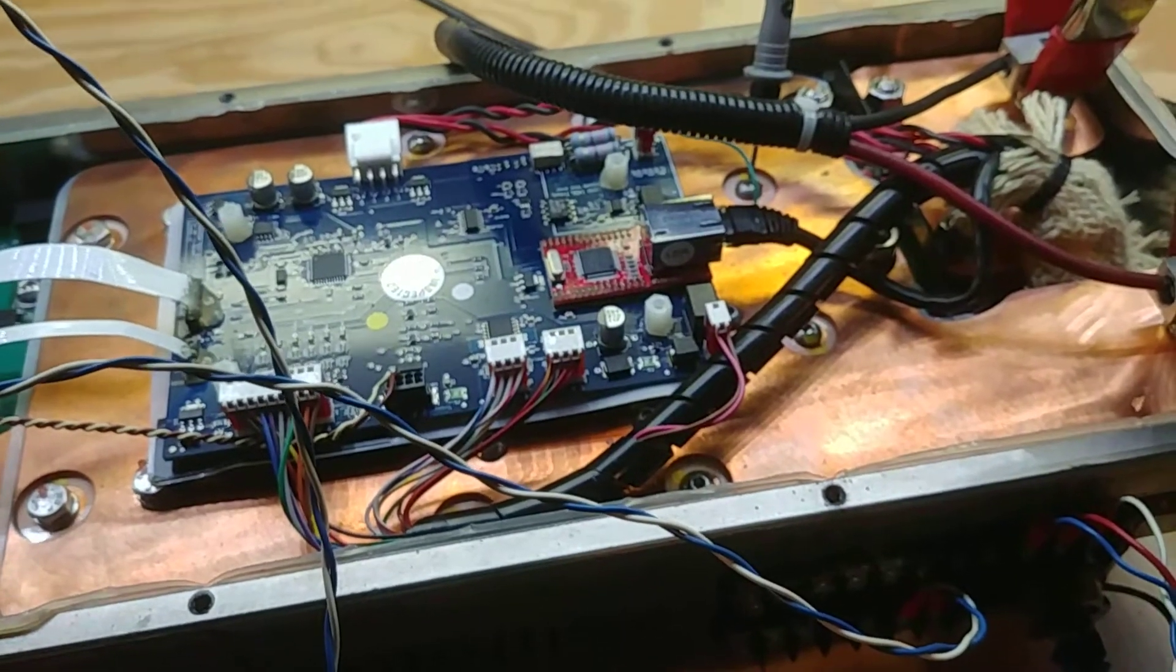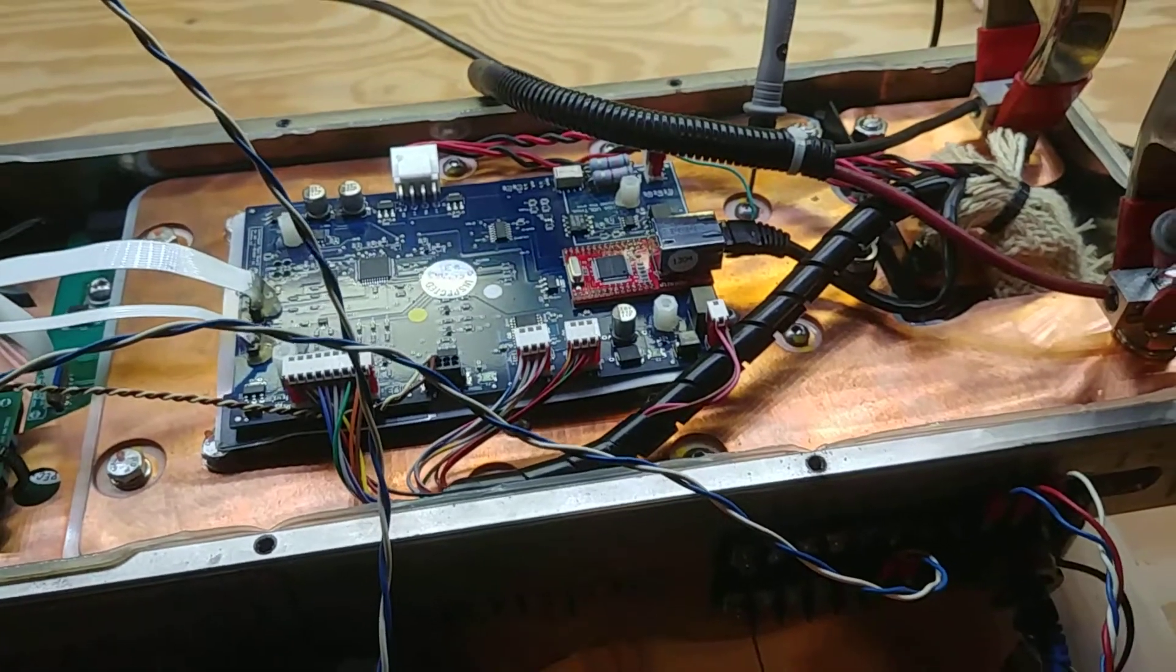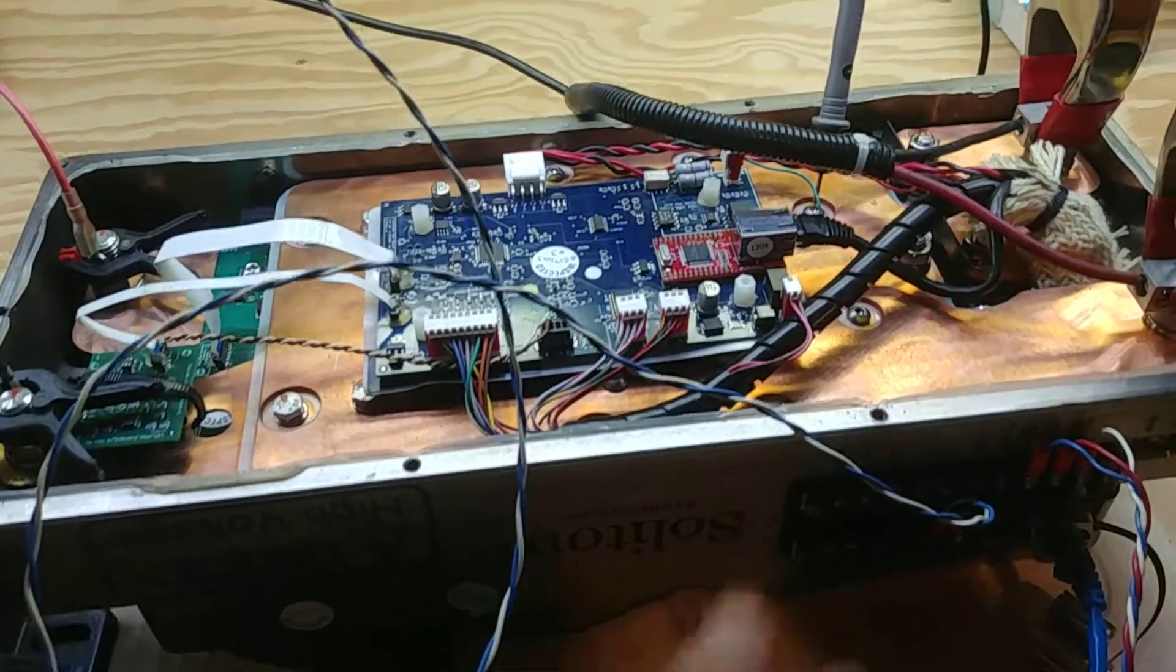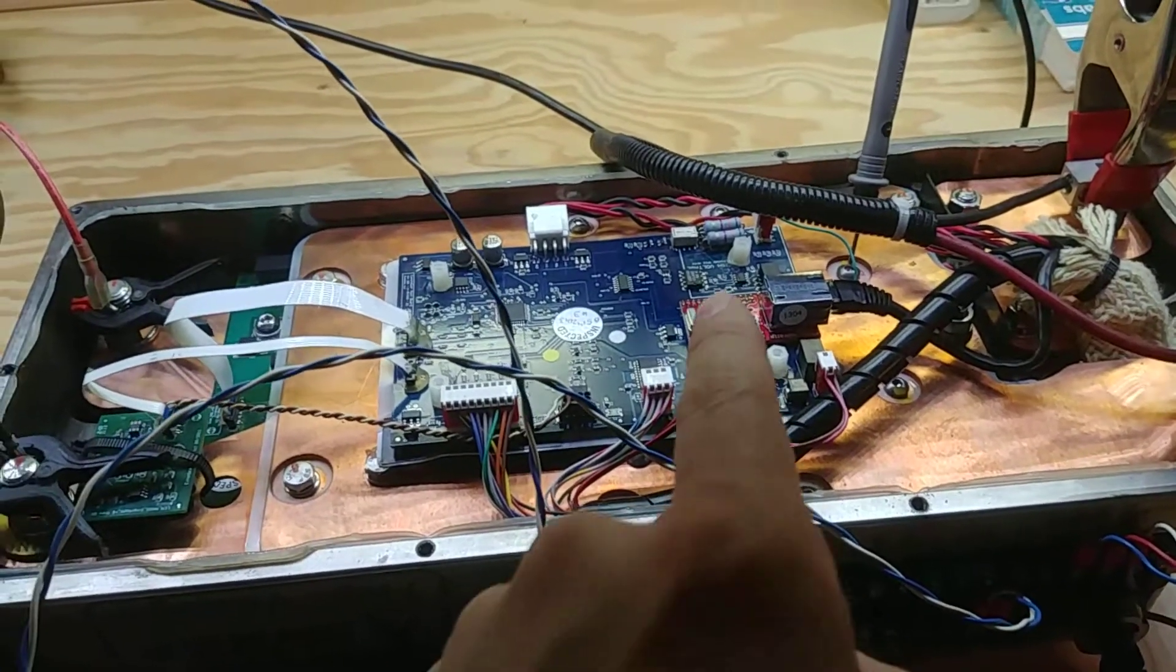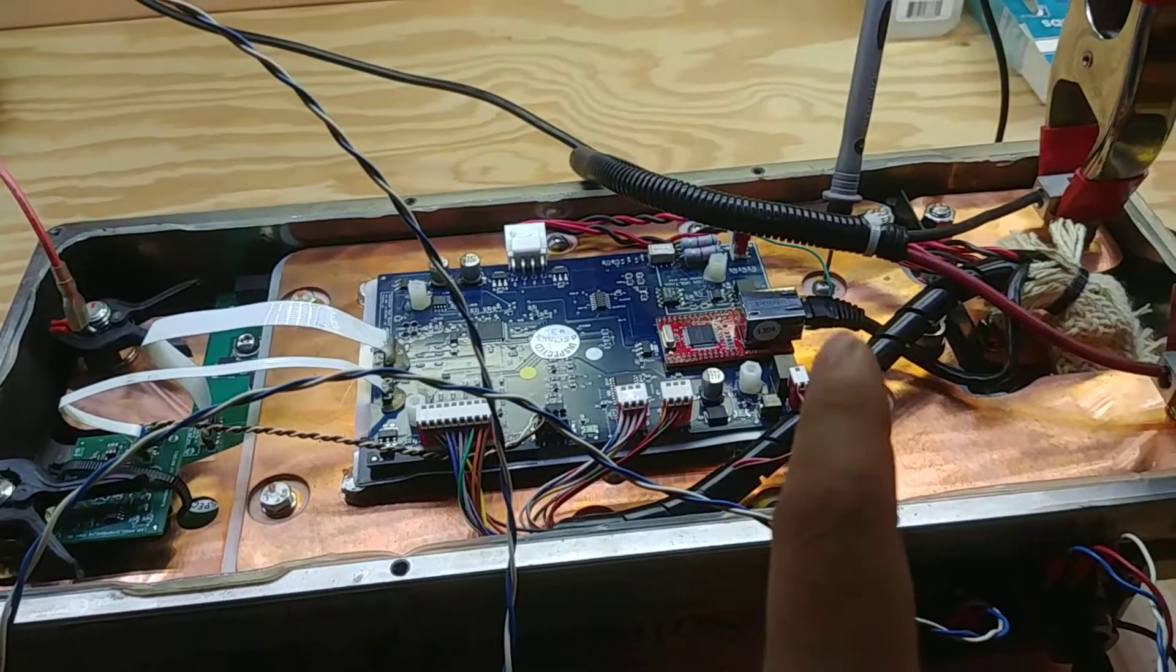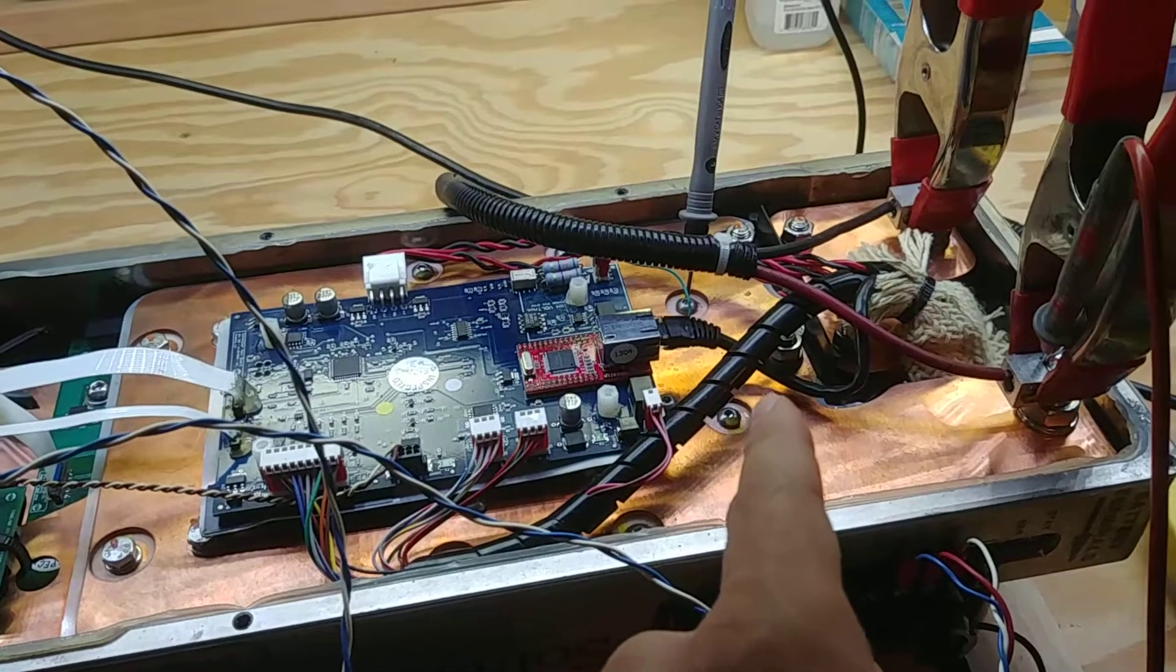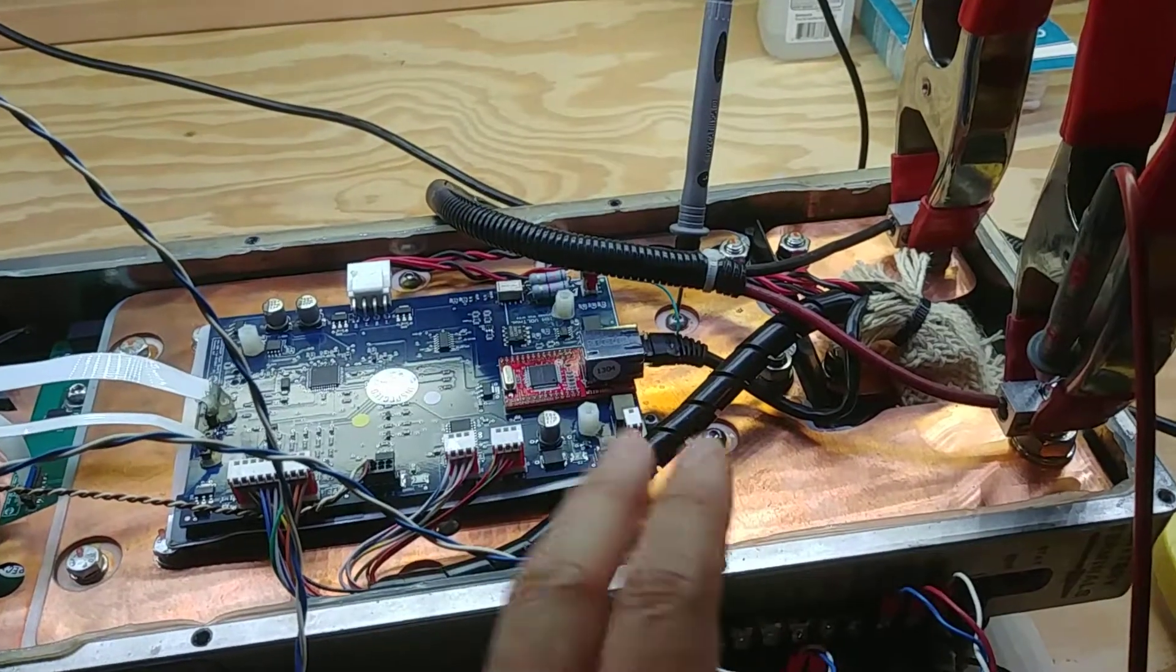So my only working theory is the battery had just enough voltage to get the drive to power up and everything. Pre-charge closed, but the contactors didn't have enough voltage to pull them in.